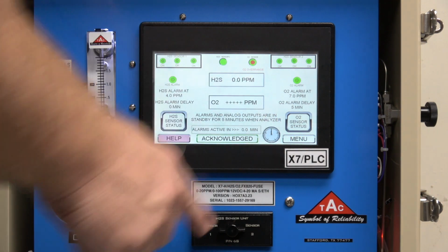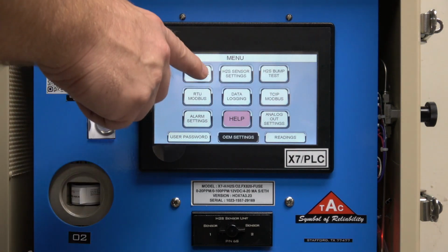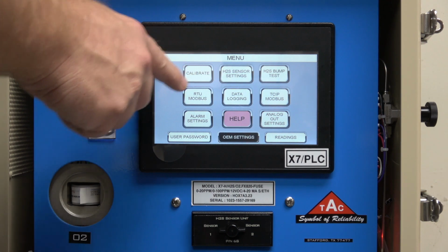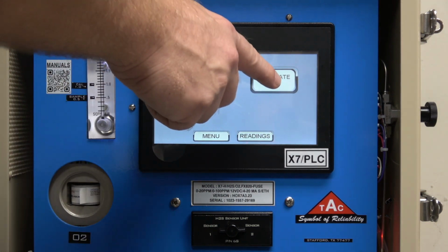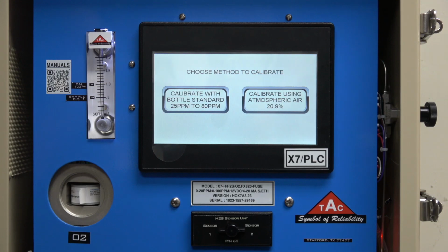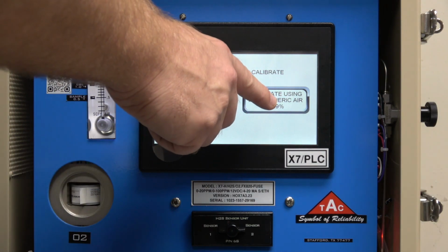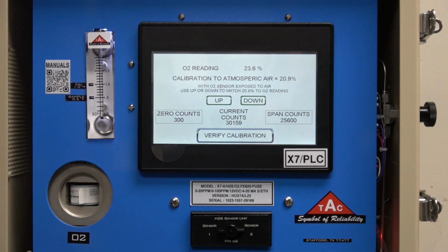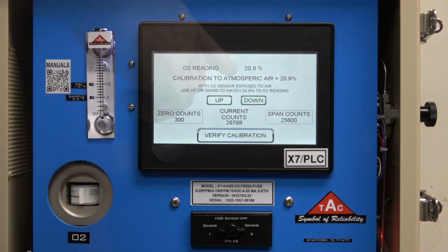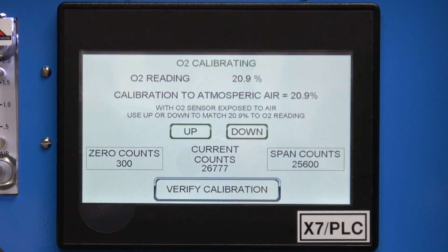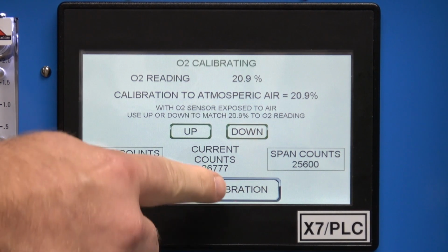Step 2. Atmospheric calibration. Press the menu button on the controller followed by calibration button. Select Calibrate O2 followed by Calibrate using atmospheric air. Using the up and down button, adjust the O2 reading to 20.9%. After 10 to 12 seconds, the reading should settle to 20.9%.